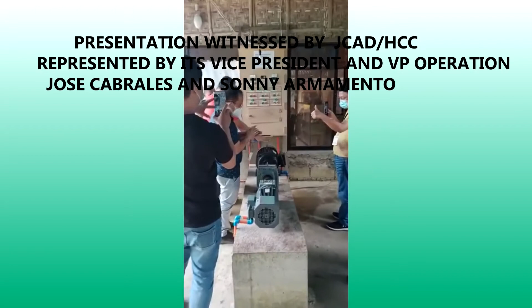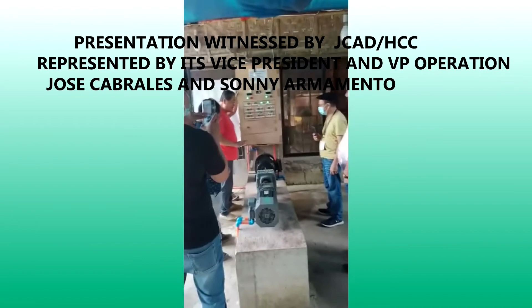So this one is 12 kilowatts minus 2.2 kilowatts. This is the load, 6.36 amperes, that is 1 kilowatt, and then there is 7 watts upstairs. So 12 kilowatts minus 2.2 gives 9.8, and minus the efficiency loss we have 8.9. Completely independent now. So we will put a load. 500 watts each bulb. Okay, 1,000.